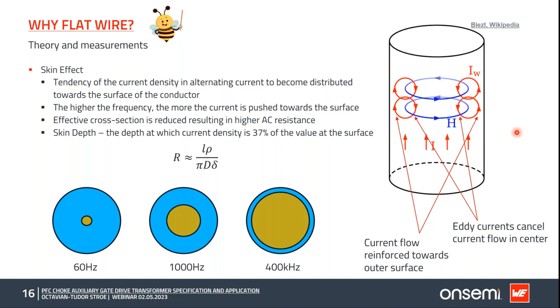This creates increased AC resistance. This happens because, as shown in the image to the right, as the current passes through the conductor it generates a magnetic field, H, that induces circulating eddy currents inside the conductor. If you look closely at the direction of these eddy currents, you'll notice they cancel some of the main current passing through the center of the conductor, and reinforce the current to the sides, so to the skin, close to the outer surface.